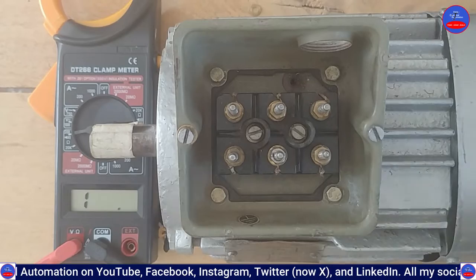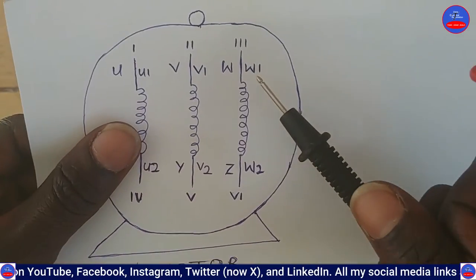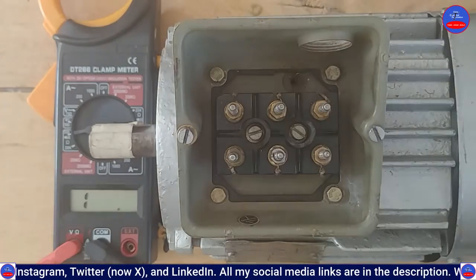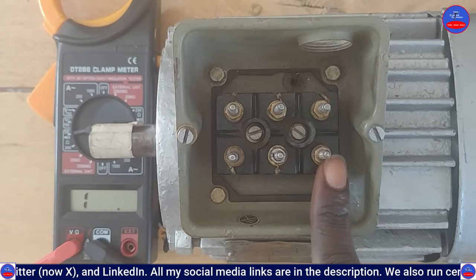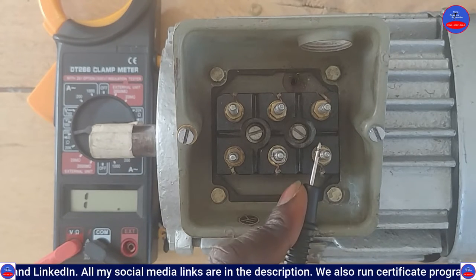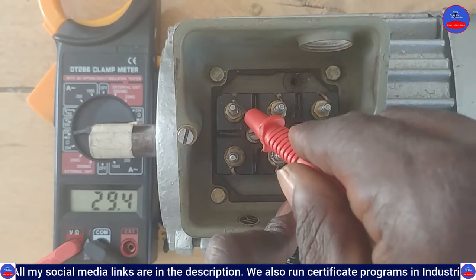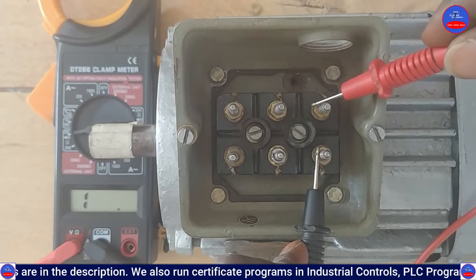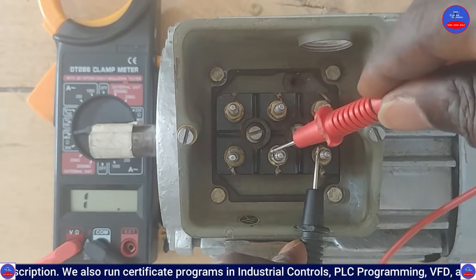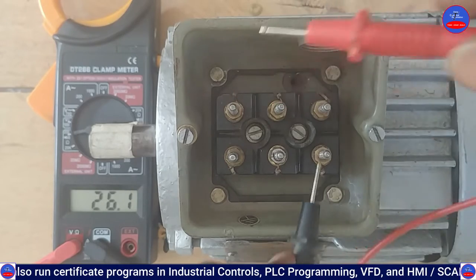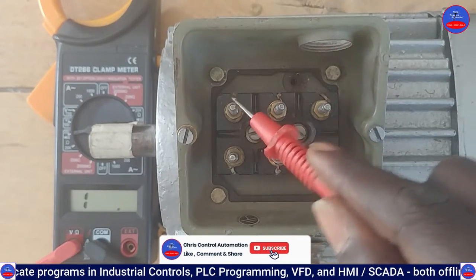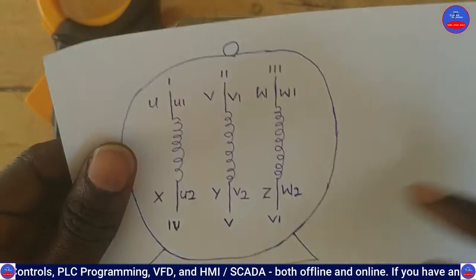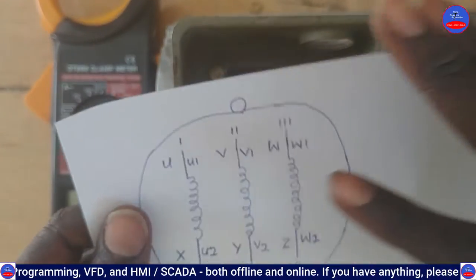Now let's test W1 and W2 — that is winding three. This is my W1. Let's put the lead here and start. There is a reading here. No reading... no reading... no reading... but there's a reading here. So this is automatically my W2. W1 and W2 confirmed.